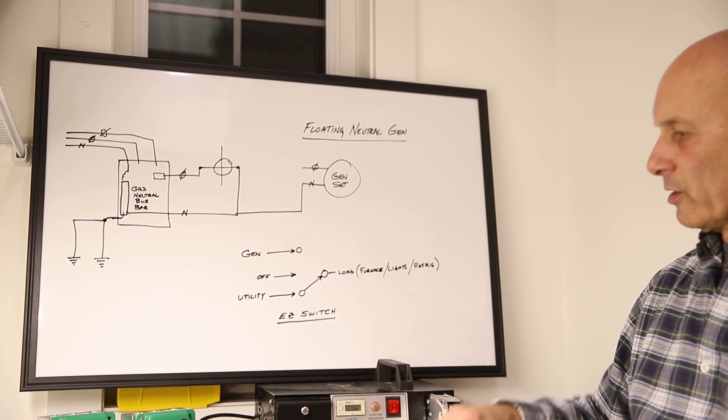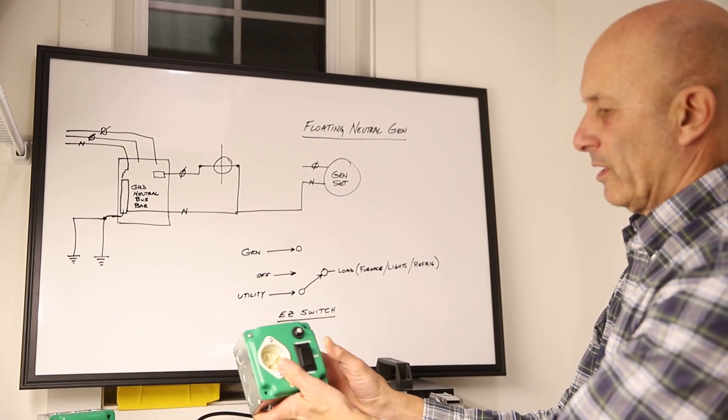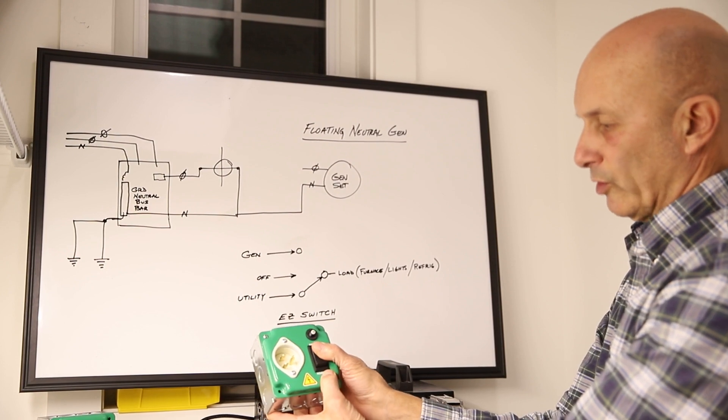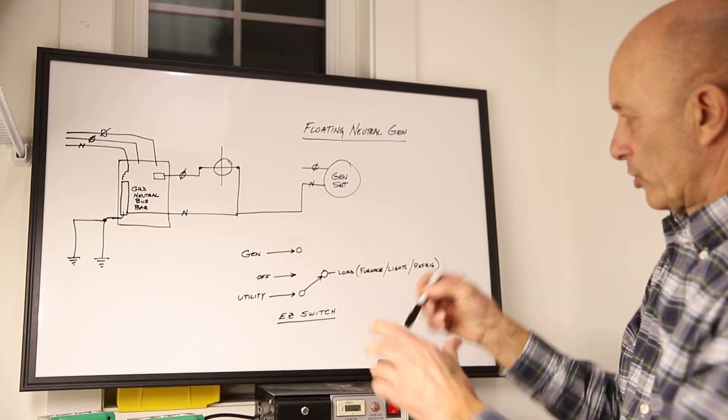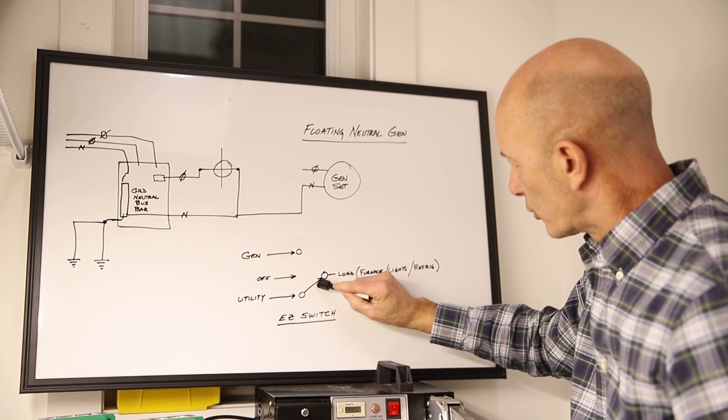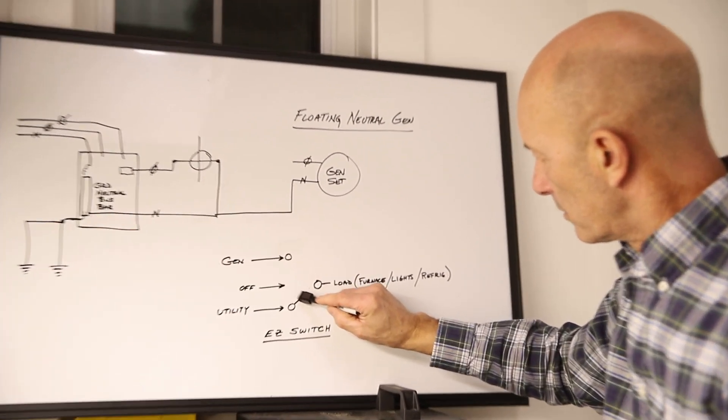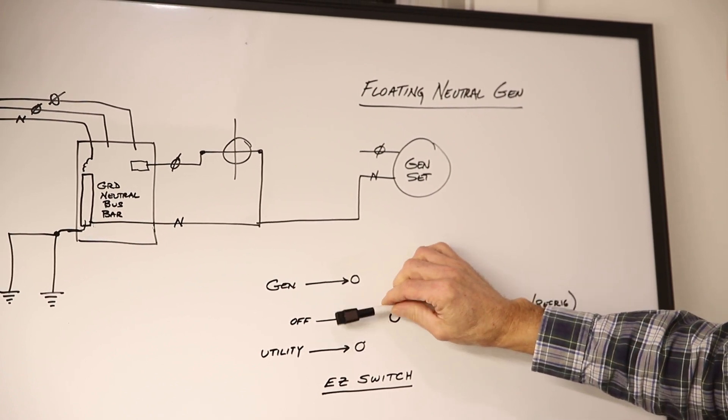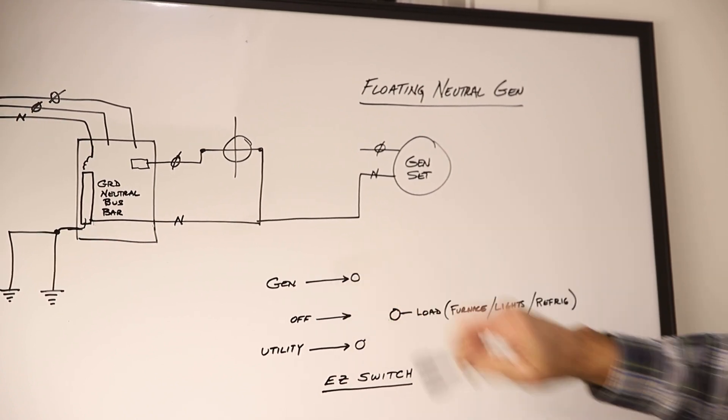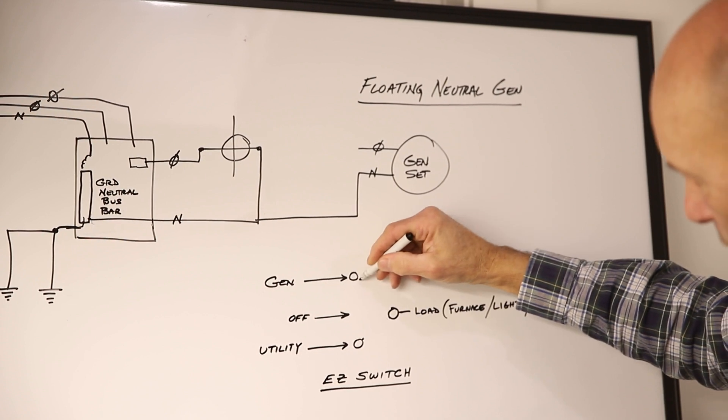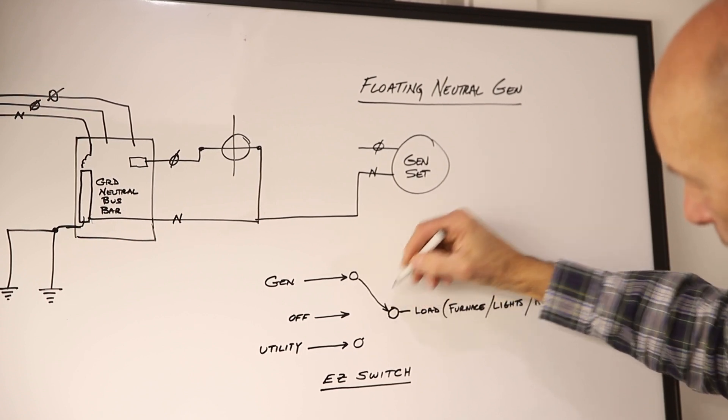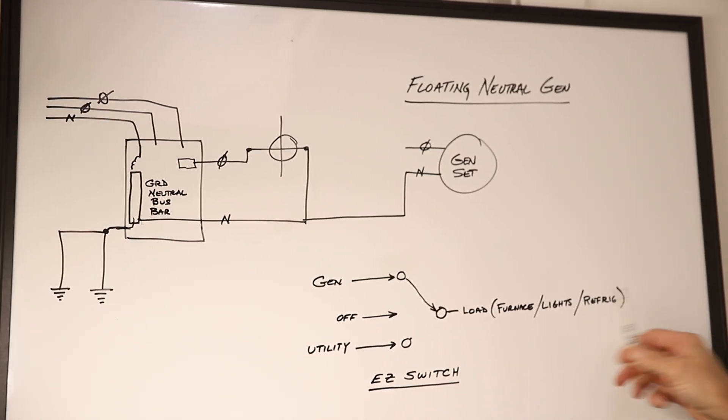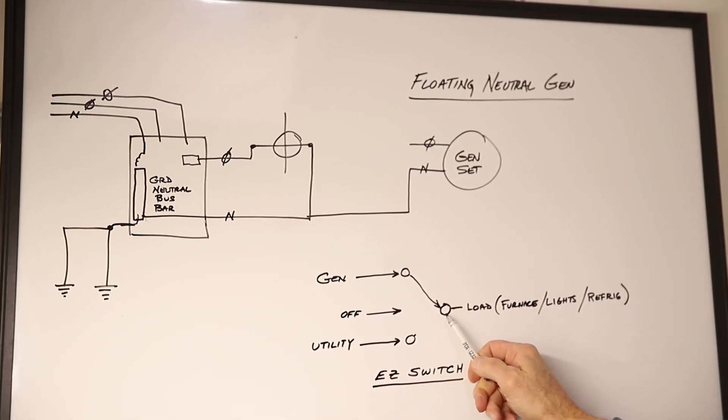When you switch our switch from the normal position from the utility to the generator you go through an off position. So physically our switch does this. Our switch goes from here, goes through the off and then comes up and connects to the generator position. So now your power from your generator is coming in going straight to the load. There is no physical connection here.